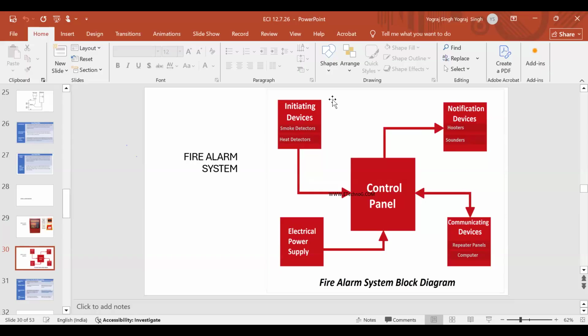The wiring system is similar, but instead of taking power from the source to that termination, here a signal is coming from that termination to this control panel. The control panel is responsible for sending power to this. If it detects, it will send a signal over here in the control panel. The control panel will immediately tell the hooters and sounders that there is some fire. So people will get to know that some emergency has been created.